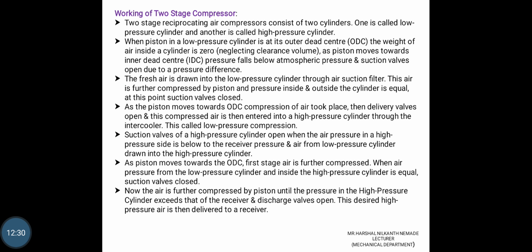Working: when the piston in the low pressure cylinder is at outer dead center, the weight of the air inside the cylinder is zero, neglecting the clearance volume. As the piston moves towards the inner dead center, the pressure falls below the atmospheric pressure. The suction valve opens due to the pressure difference.